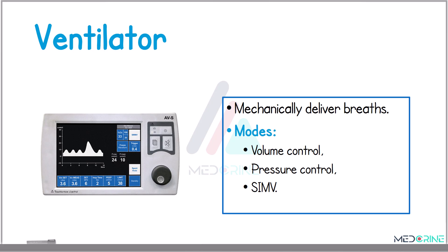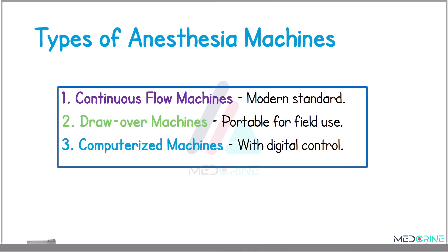A ventilator delivers breaths when the patient is under general anesthesia. There are a number of modes that can be set in this ventilator, for example the volume control mode, the pressure control mode, and synchronized intermittent mandatory ventilation, or SIMV mode.